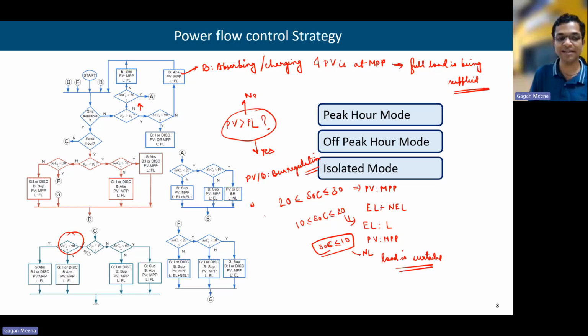If SOC is less than 90%, then what will happen? Excess generation from the PV, which is operating at the maximum power point, will go into charging the battery. And the grid will remain idle or disconnected. No need to take supply from the grid. The PV generation is sufficient to meet the load as well as to charge the battery.